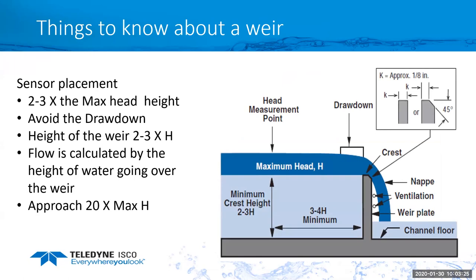But let's take a closer look at the weir. As far as the sensor placement, one of the bigger questions I get is where I should read the level. Where do you measure the level from? We have the head measurement point, which is 2 to 3 times the maximum head height of water going over the top of the weir. And that's going to be determined by what your expected flow rate is through that channel. And why that's important is that if you have the sensor too close to the weir wall, there's a drawdown effect. And as you can see with this drawing, it draws down and the level could be a little bit lower closer to the weir wall, which would then give you a calculated lower flow rate.